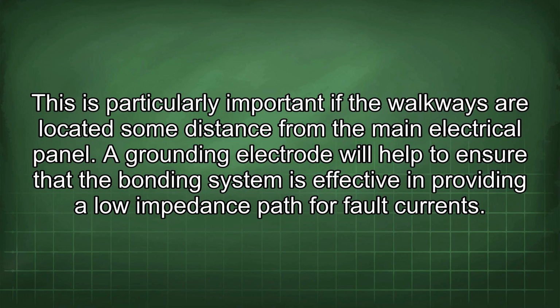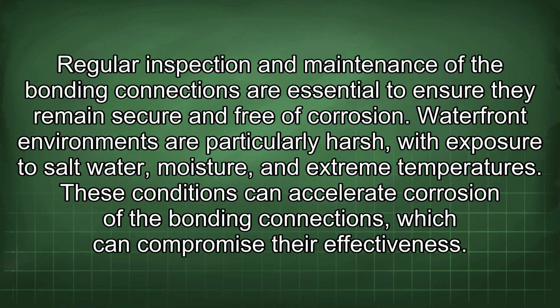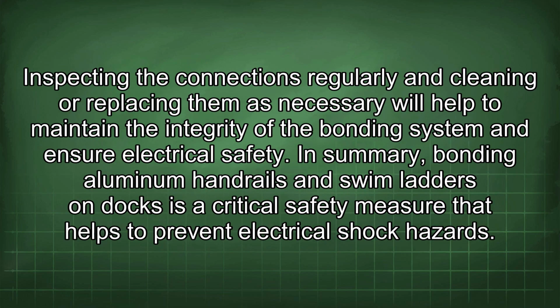A grounding electrode will help to ensure that the bonding system is effective in providing a low impedance path for fault currents. Regular inspection and maintenance of the bonding connections are essential to ensure they remain secure and free of corrosion. Waterfront environments are particularly harsh, with exposure to salt water, moisture, and extreme temperatures. These conditions can accelerate corrosion of the bonding connections, which can compromise their effectiveness. Inspecting the connections regularly and cleaning or replacing them as necessary will help to maintain the integrity of the bonding system and ensure electrical safety.